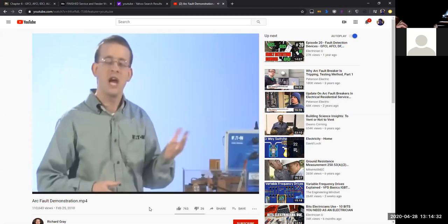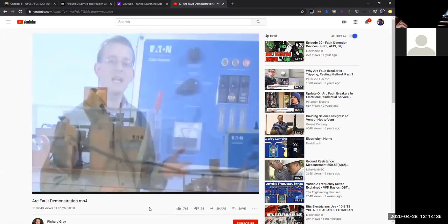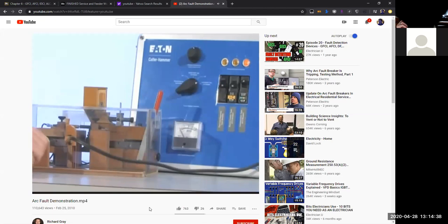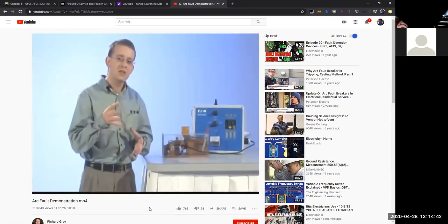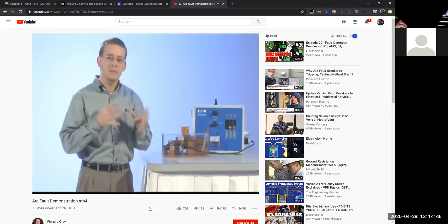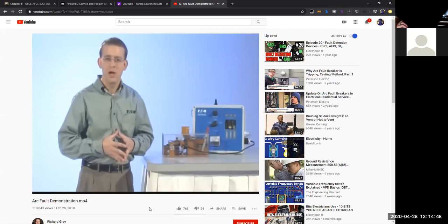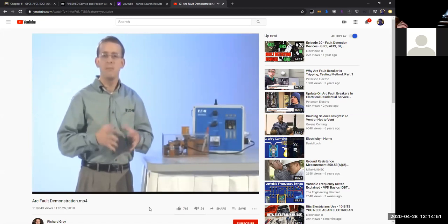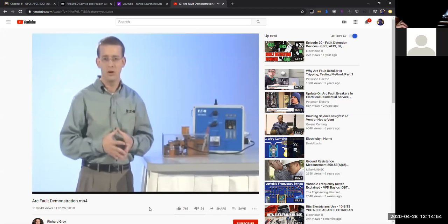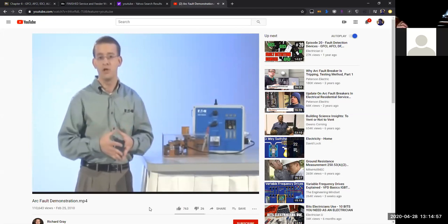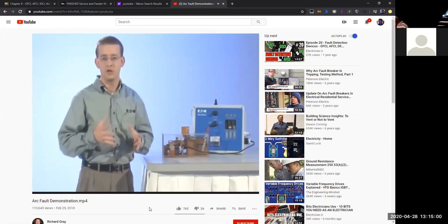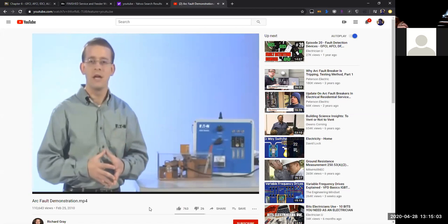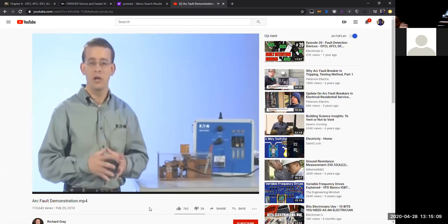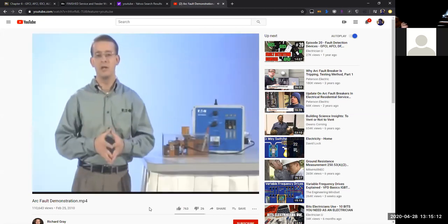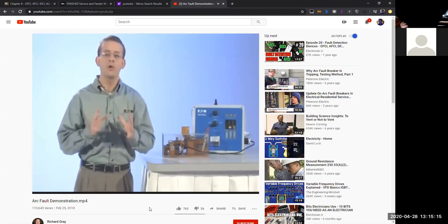The challenge with designing the combo AFCI breaker is that every electrical device will create arcs during its operation. When the contacts close or separate, they create these small arcs, just as I was trying in the demo here. The protective device needs to differentiate between these operational or intentional arcs, such as the flipping of a light switch or operation of a motor, and the non-operational or dangerous arc. The combo AFCI breaker is designed to ride through these operational arcs and only look for sustained low current arcing before tripping.